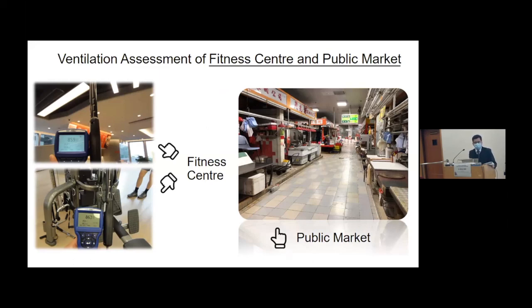For fitness centers, it was observed that fresh air was mixed with recirculation air, which greatly reduced the fresh air intake capacity, resulting in high CO2 concentration within parts of the premises. Also, some air intakes and outlets were found close to each other, and short circuit of air was observed. For the problem on fresh air intake, simply reducing the air damper on the recirculation air ductwork could solve the problem. All in all, proper ventilation equipment was installed at the fitness center. Only slight adjustment on the setting will be able to create an environment that is less vulnerable to the spread of disease.